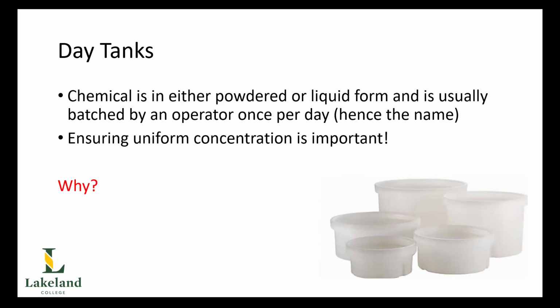Now, what I mean by this, and also why this is a disadvantage, is because it incorporates human error, or I should say operator error. The idea is, let's say for example, I am going to batch a chemical day tank. I test the concentration and I now batch enough chemical with enough water to get my concentration. And I've batched it just right. Now let's say that the next person that comes along and batches the next set, they batch it slightly weak.